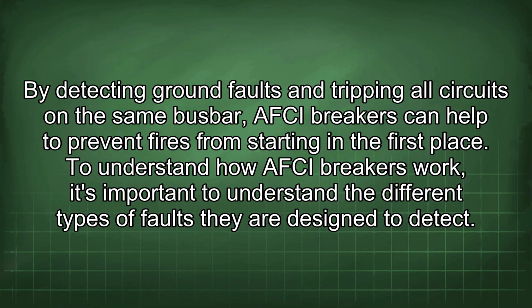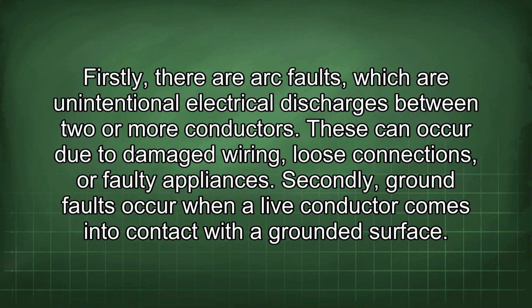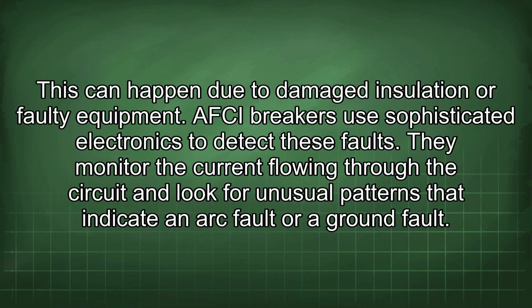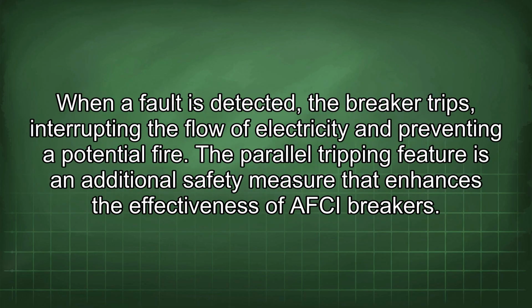To understand how AFCI breakers work, it's important to understand the different types of faults they are designed to detect. Firstly, there are arc faults, which are unintentional electrical discharges between two or more conductors. These can occur due to damaged wiring, loose connections, or faulty appliances. Secondly, ground faults occur when a live conductor comes into contact with a grounded surface. This can happen due to damaged insulation or faulty equipment. AFCI breakers use sophisticated electronics to detect these faults. They monitor the current flowing through the circuit and look for unusual patterns that indicate an arc fault or a ground fault. When a fault is detected, the breaker trips, interrupting the flow of electricity and preventing a potential fire.